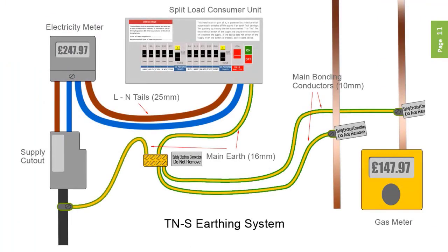TNS means terra-neutral separate, which means earth and neutral conductors are separate coming into the installation. The outer sheathing of the supply cable — either steel wire armour or often lead — is used as the incoming earth conductor. This is more often found on old installations, and is easily identifiable by the earth connection being made directly onto the cable sheath.